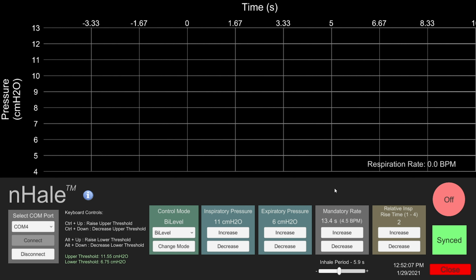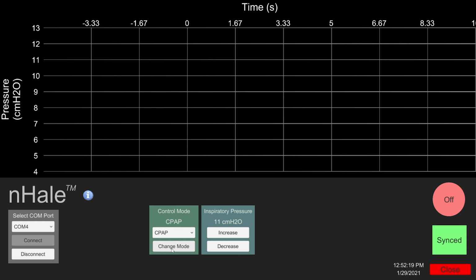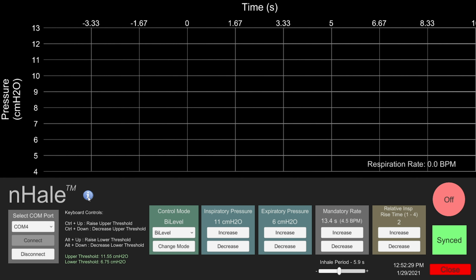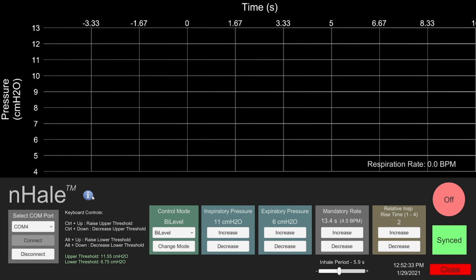If you would like the nHale to operate as a continuous positive airway pressure device, select CPAP. Once CPAP is selected, click Change Mode and set the therapy pressure to a value that is comfortable for the patient. To view device details and configure data logging and alarm settings, press the Information button. Version and calibration information, as well as pressure statistics, are shown here.